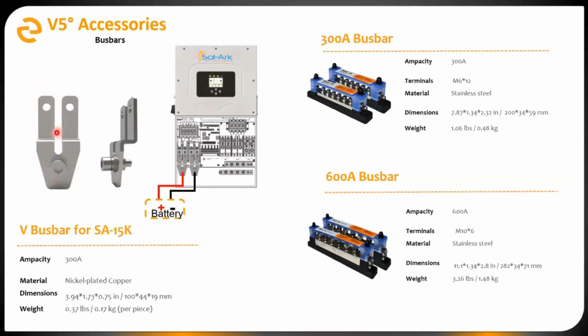These V bus bars aren't required for Sol-Ark 15K installs. If you didn't use them, typically you're looking at doubled up, or 2 sets of 2-aught cable, between the battery bank and the inverter. When we do use these V bus bars, that lets us do a single cable run with 4-aught instead of the doubled up 2-aught. I don't think there's a right or wrong way, there's pros and cons for each, but just know this is an option we offer, and I think it does a really good job of cleaning up an installation, especially when you have a bunch of inverters. It reduces the amount of cables you have to run for the most part.